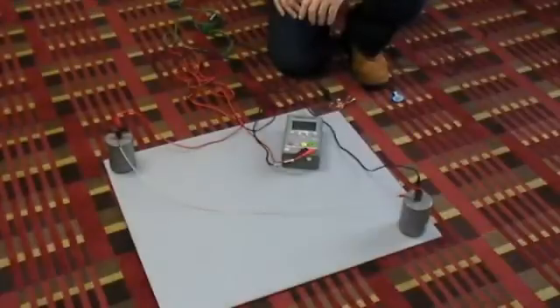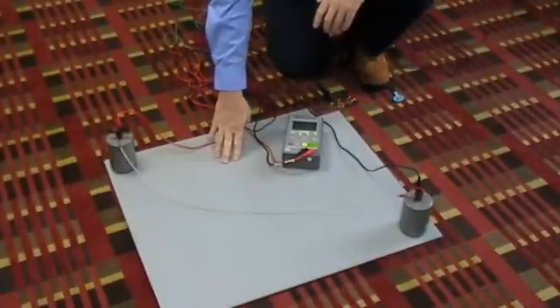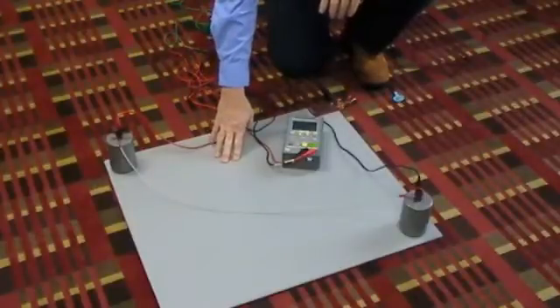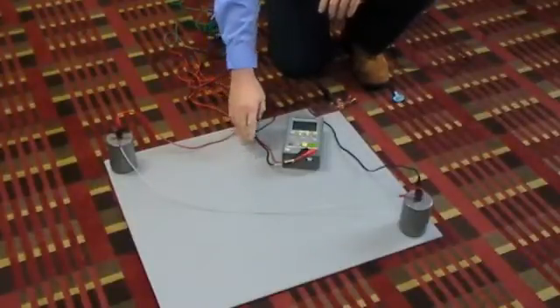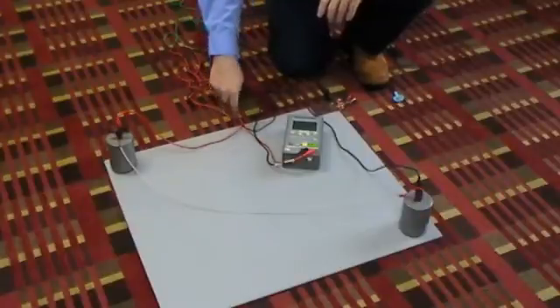Now we're going to perform the second part of the test, which is a groundable point on the floor to ground, and run the test voltage through the meter, through the floor, and back to ground.